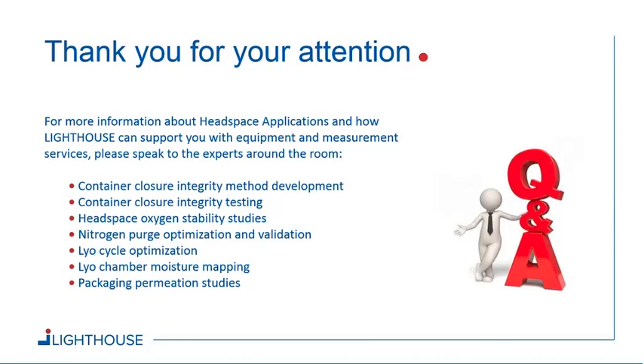I have to say, personally, I don't know of a specific example that comes to mind. I'm guessing, I'm sure there are. I do know of a number of customers who have submitted for the 2008 guidance, which was about doing CCI tests in lieu of sterility testing for the stability protocol. I do know of clients who have submitted Headspace as the CCI test in lieu of sterility testing, and that was accepted with no comments. But for the initial qualification of CCI, I'm not sure.